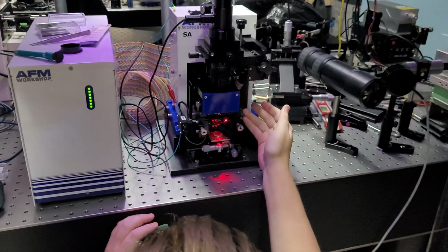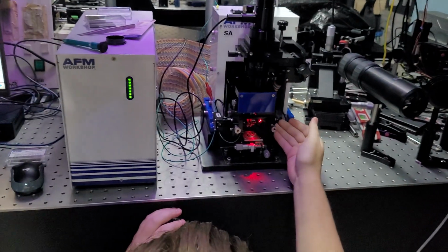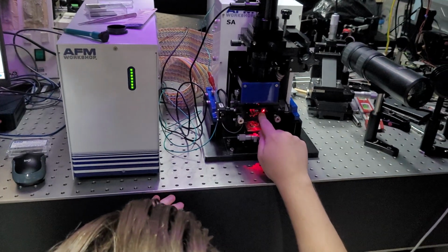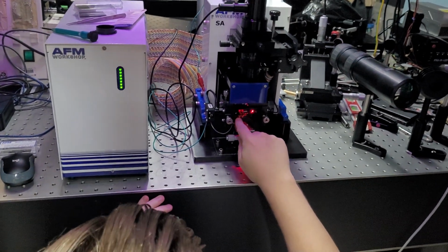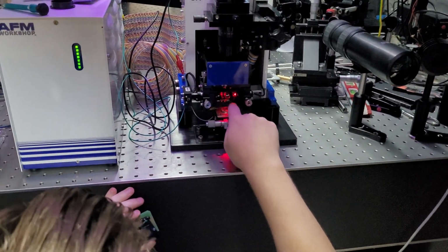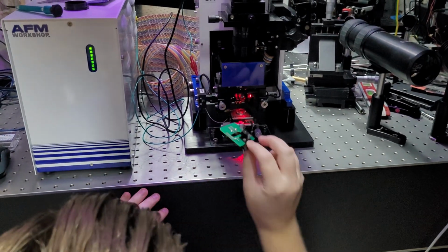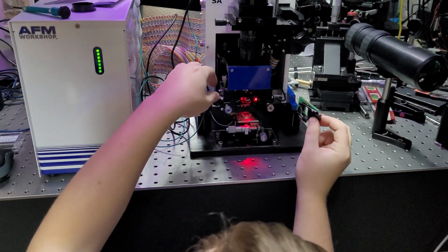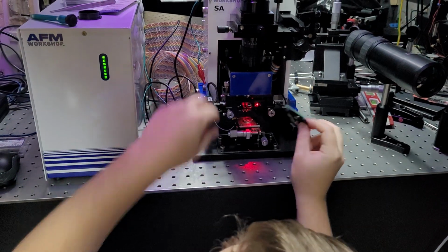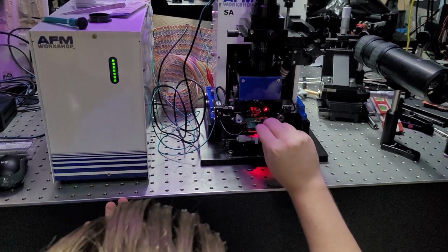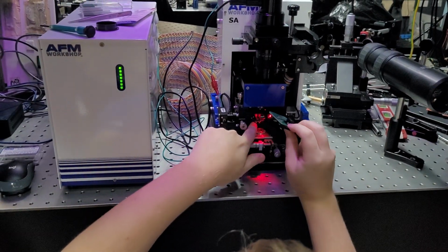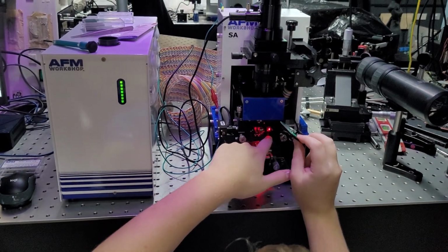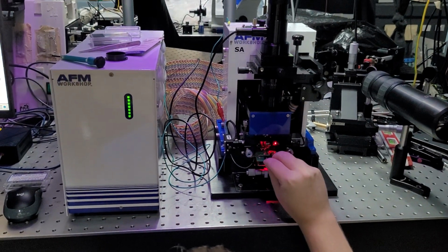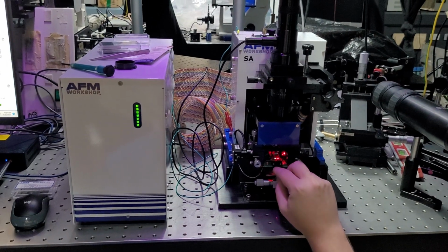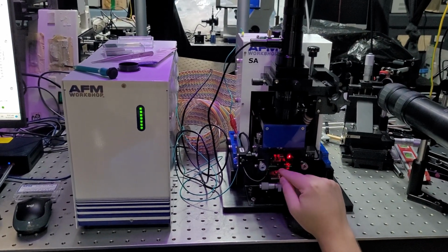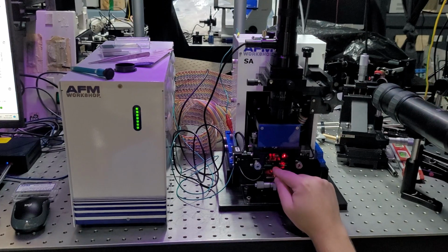So this is where on the right we have our laser module. Right here we have our mirror. We have a kind of little slotted area where this probe holder will slot in. And then we have our photo detector here. So if I go ahead and place this, as I said before, there's kind of slots here and here that it rests on. So if I go ahead and place it onto there, it sits on track, and then you just push it back and it will magnetize to the very back.